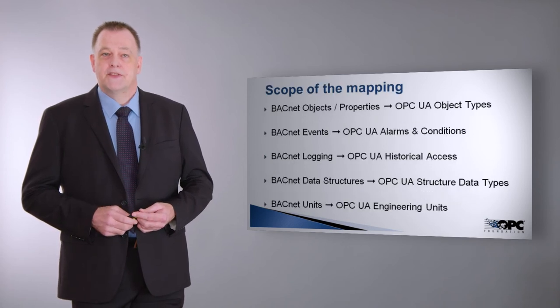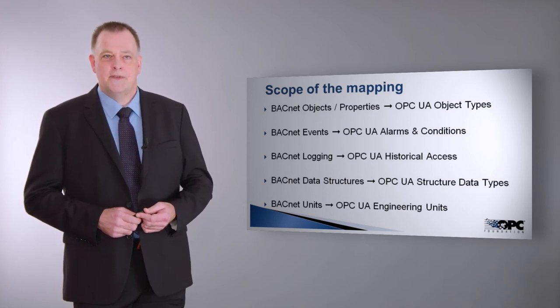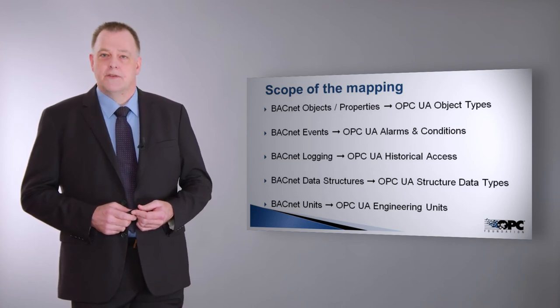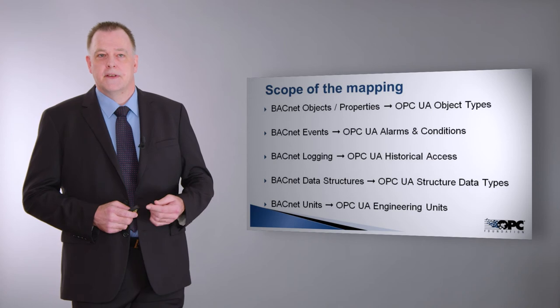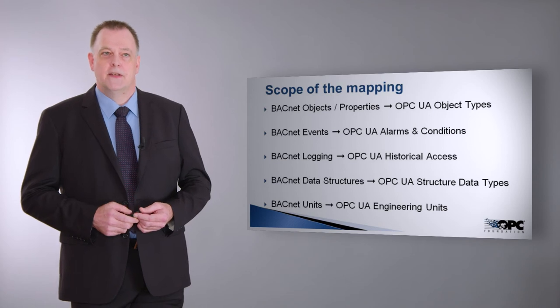The scope of the mapping covers how to map objects and properties into the OPC UA types, events into OPC alarms, logging into OPC historical access, data structures into OPC UA structure types, and of course BACnet units into the OPC engineering units.